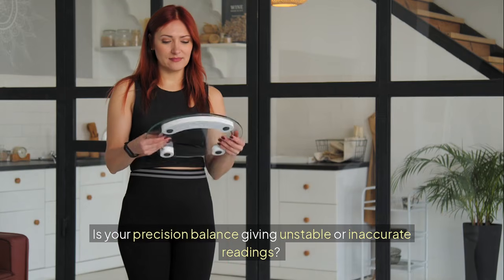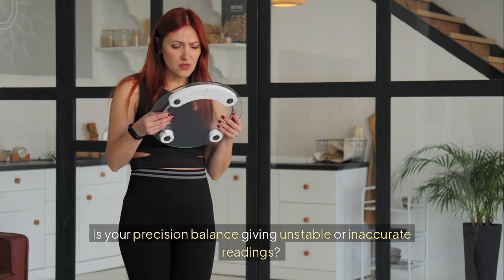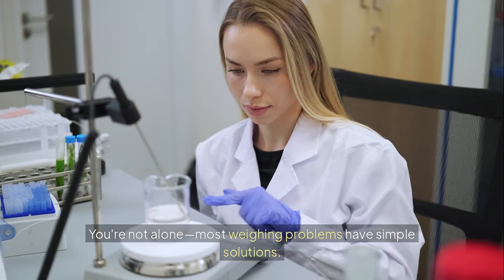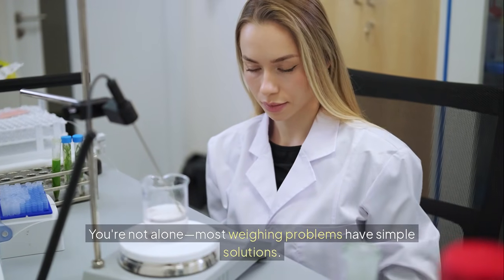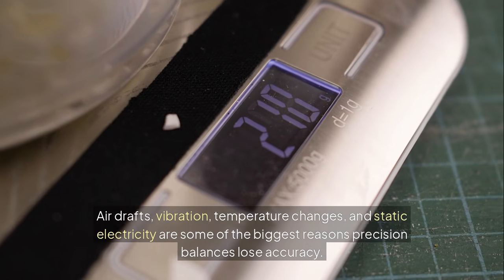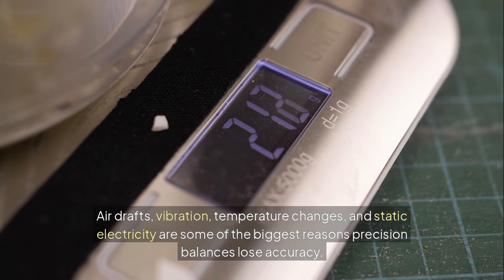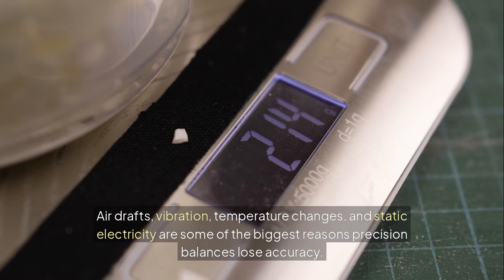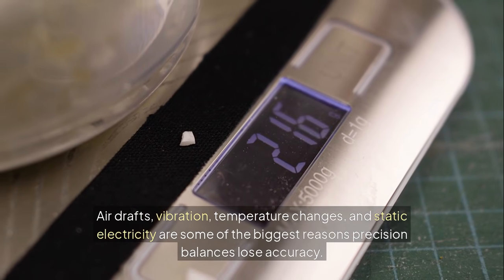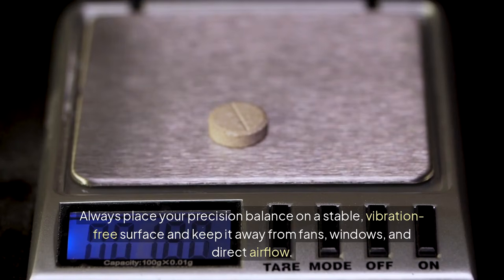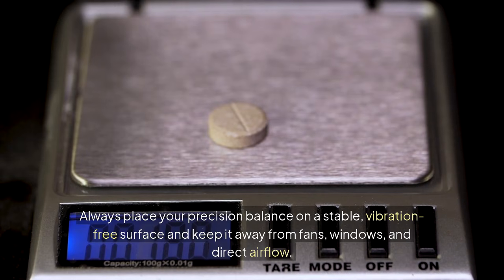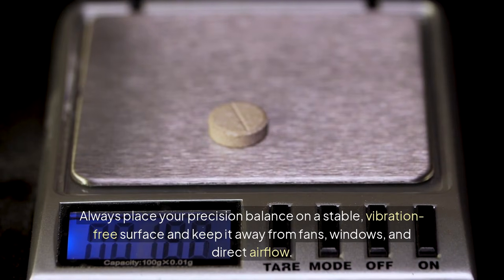Is your precision balance giving unstable or inaccurate readings? You're not alone. Most weighing problems have simple solutions. Air drafts, vibration, temperature changes, and static electricity are some of the biggest reasons precision balances lose accuracy. Always place your precision balance on a stable, vibration-free surface and keep it away from fans, windows, and direct airflow.